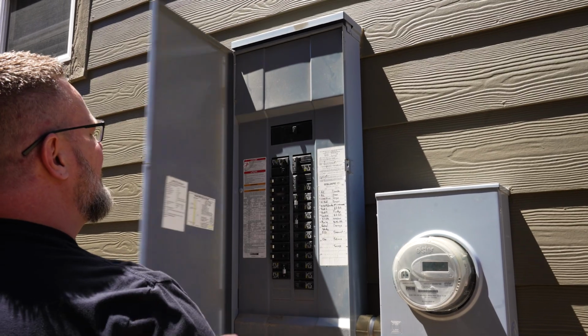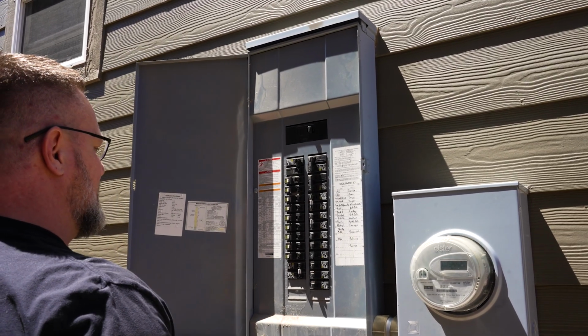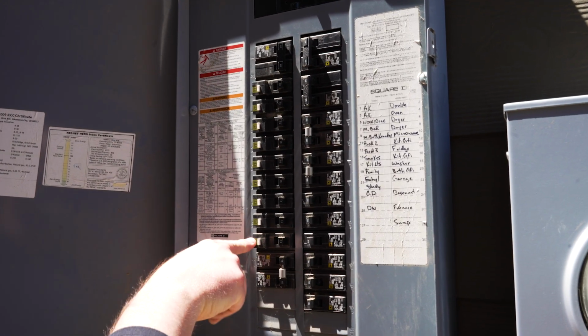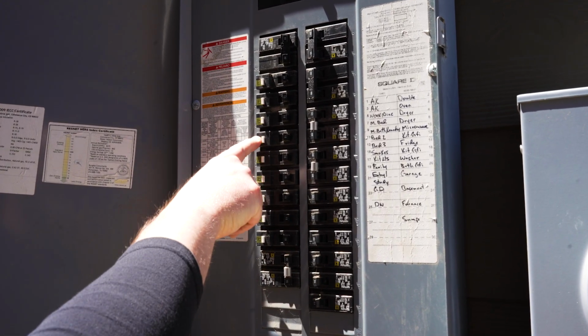Labeled electrical breakers, if they're labeled. When you pull the dead front cover off, is it the one wire, one breaker kind of rule, or is that double tapping? And of course, overheating fuses, if there's burn marks, that kind of stuff we're looking for.